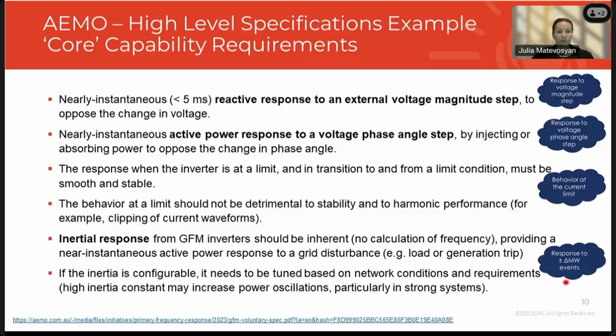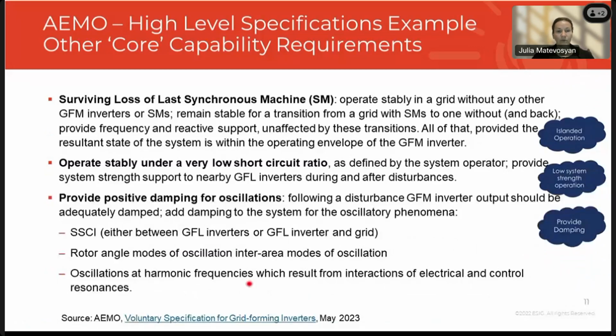And then if inertia is configurable, it needs to be tuned based on network conditions, and there are requirements for the inertia constant, because a high inertia constant may increase power oscillations and be particularly detrimental in strong grid systems. All right, so continuing on core requirements, they have this surviving loss of the last synchronous machine, and I'll come back to this more as I go through other requirements. So this is a common theme associated with the definition of grid forming capability.